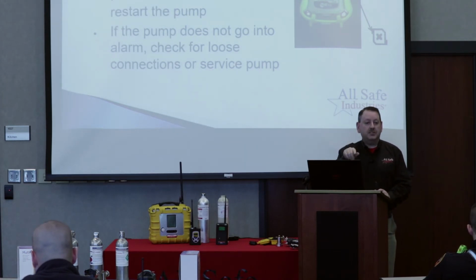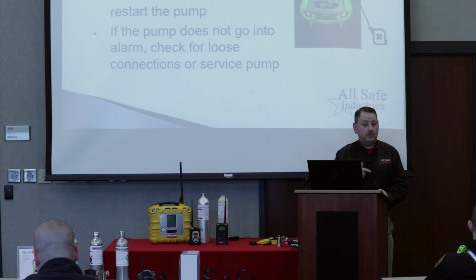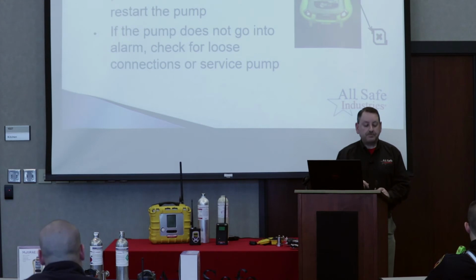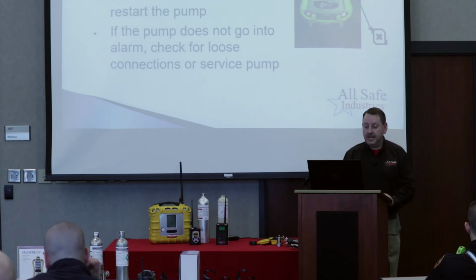So when you guys get to the end of your fresh air calibration, go ahead and test that so you've gotten familiarity with it. If the pump does not stall, well, that means it's not working properly, and you'd want to put that meter down and choose another one or turn that in for service, okay? So that's your pump stall. And again, notice the little pump icon will have an X on it to let you know that the pump stalled out. Great, sounds like you guys have that.